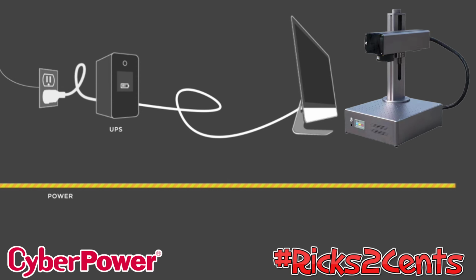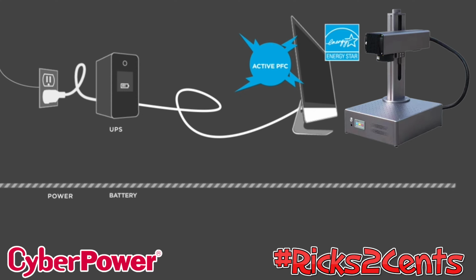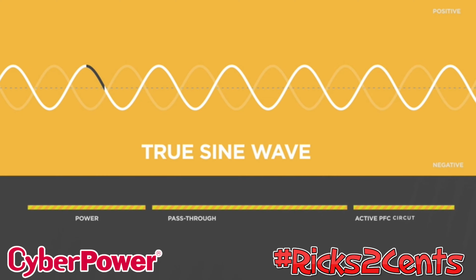Active Power Factor Correction, or active PFC, improves the energy efficiency of power supply units in newer and higher-end computers and electronics. For example, any equipment with Energy Star certification has active PFC circuitry. This technology is becoming widely used, and it requires even more consistent power. When it receives direct utility power or pass-through power, equipment that uses an active PFC circuit will function as it should. When it receives power from a backup battery, however, it may not work correctly. Here's why. Utility power arrives as a sine wave, a smooth, continuous movement between positive and negative polarity.